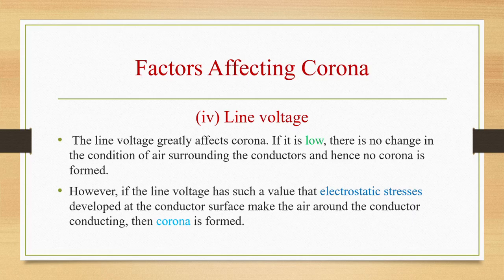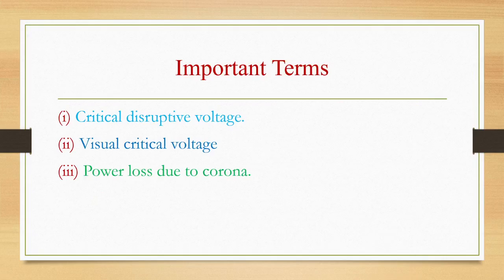If the line voltage is less, then there is no change in the condition of air surrounding the conductor and no corona will be formed. If the line voltage is increased such that the electrostatic stresses developed at the conductor surface make the air conducting, then corona will be formed. So there are basically four factors which are affecting the corona. First is atmosphere, second is conductor size, third is the spacing between conductors, fourth is the line voltage. Now let us see a few important terms.